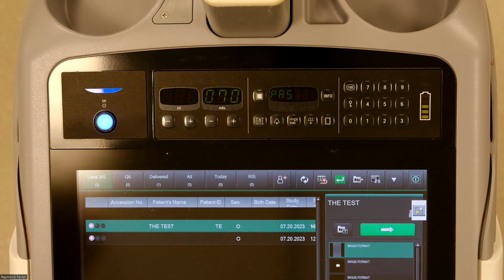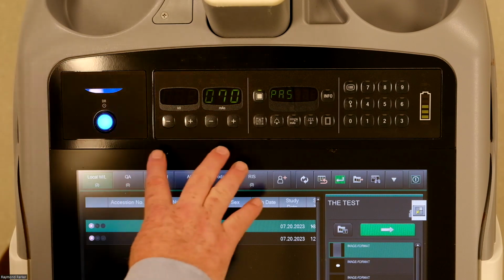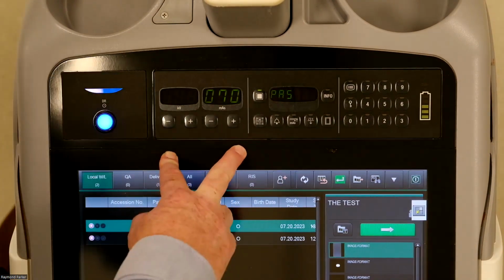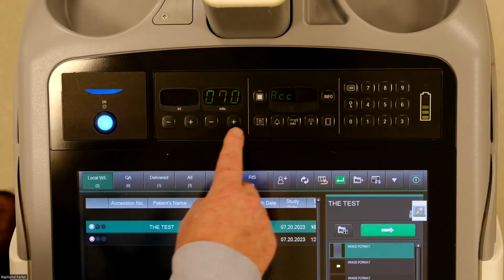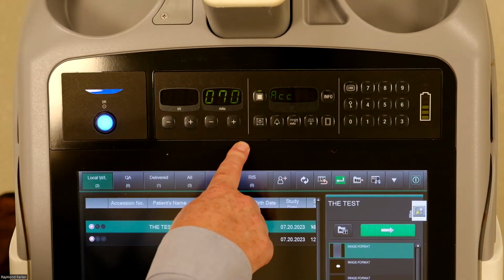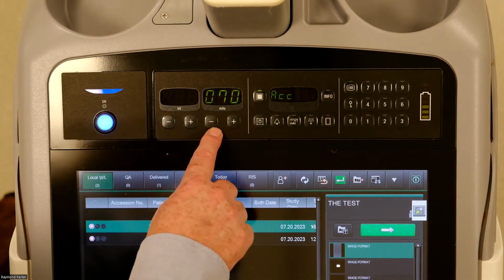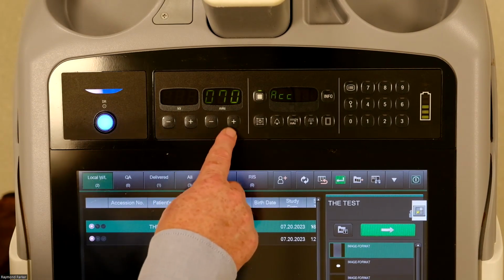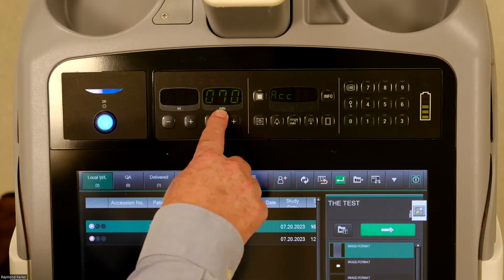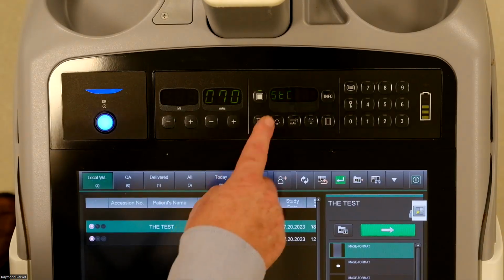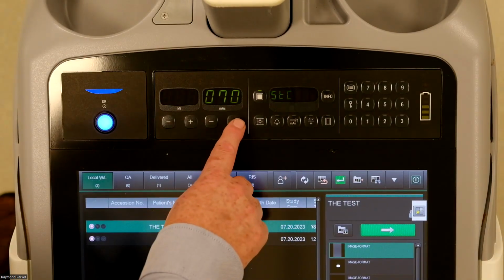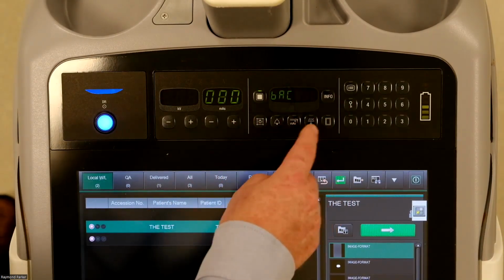Reason being, there are certain setup and tools required to recalibrate the handle if necessary, and we usually let the service control that. If you did need a little bit of acceleration, you can up that by hitting the plus or the minus, and it will be entered in the mAs field. Steering control, again, I try to avoid touching any of those.